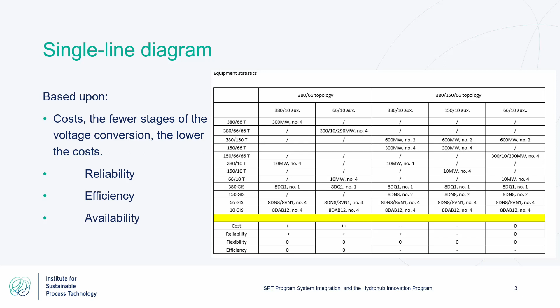If we go to the single line diagram, there we have looked at several topologies. We looked into a 380, 150, 66 kV topology. We also looked into a 380 to 66 kV topology. What is important to select the correct single line is of course the costs. And in this project, we really looked to minimize the number of voltage stages, because each and every voltage stage needs transformers.